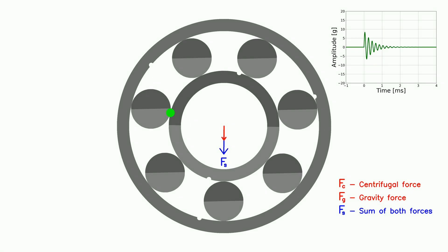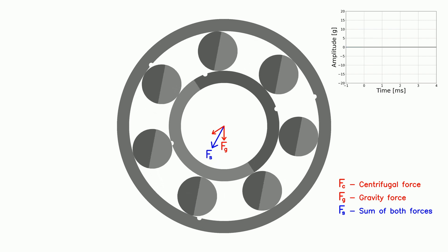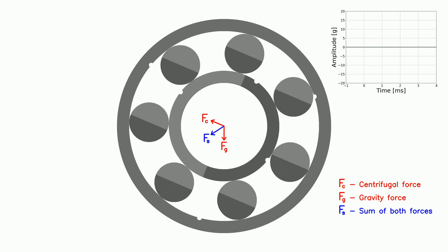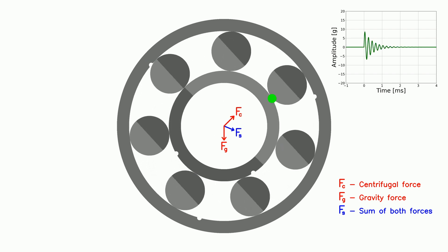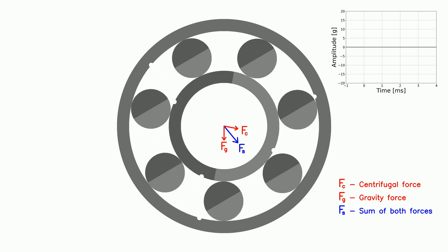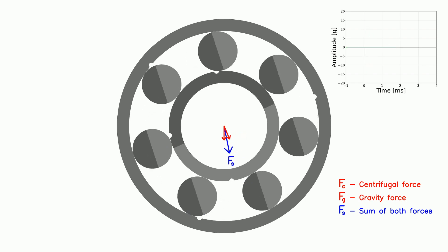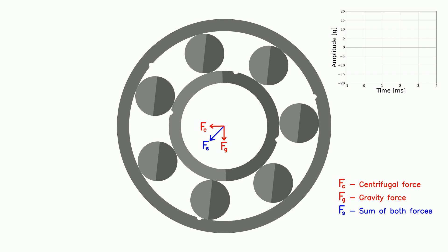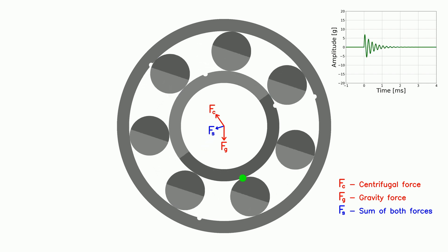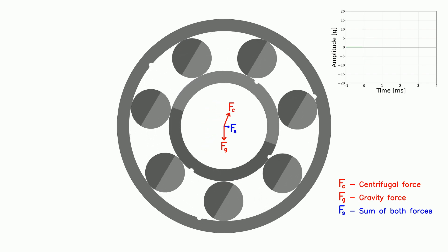If there is unbalance and a force due to the shaft's weight, they add together. Modulation happens to the outer race shocks and to the inner race shocks. It is because the sum of the forces, Fs, changes as the shaft rotates. Therefore, forces acting on faults on both races are variable.